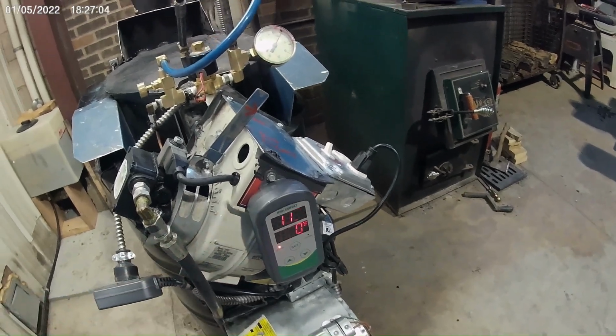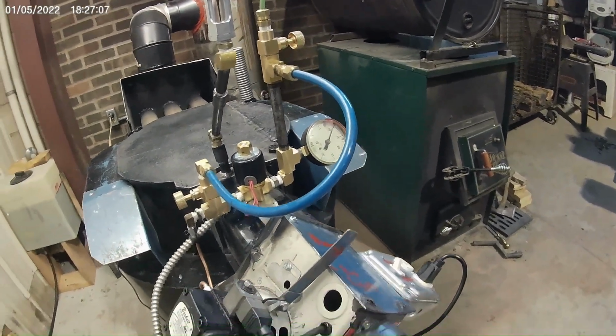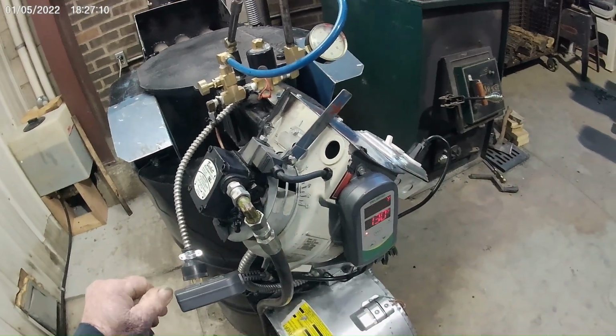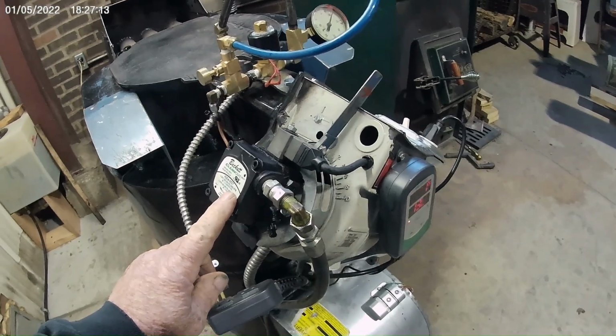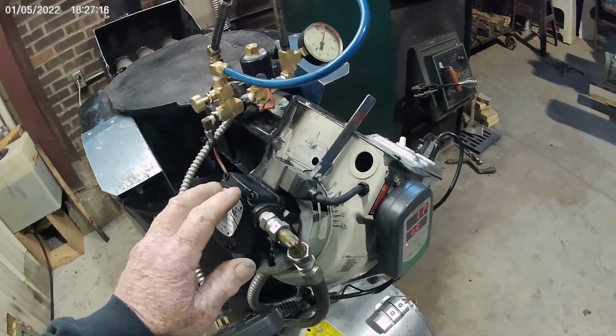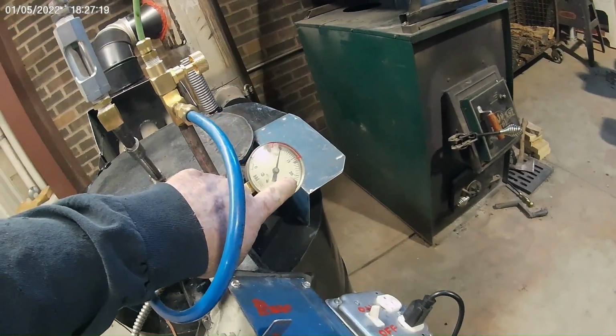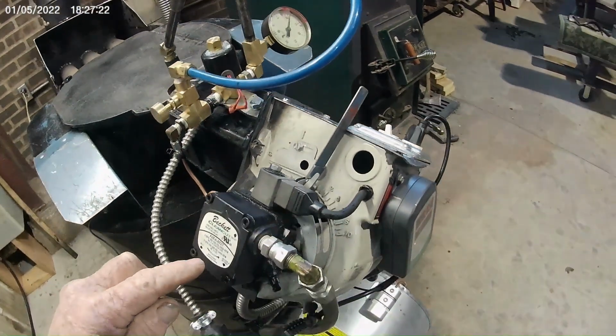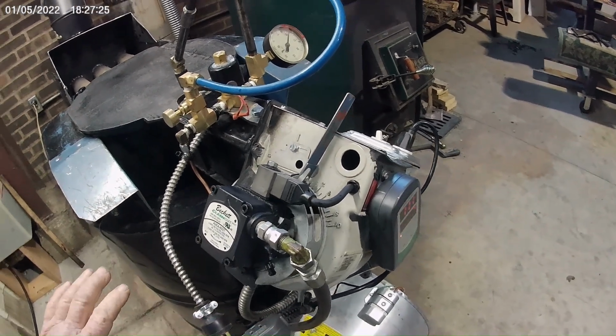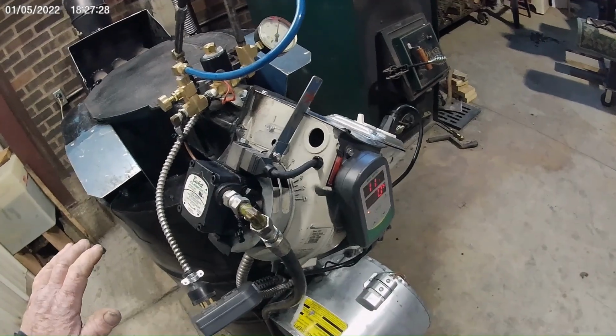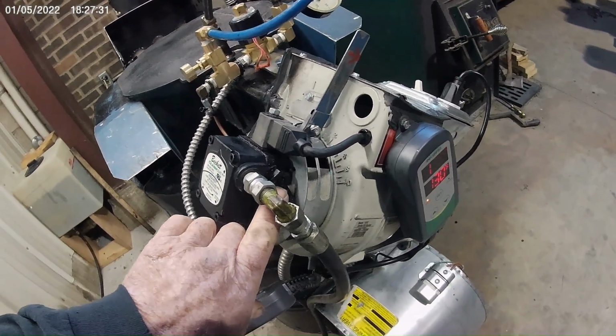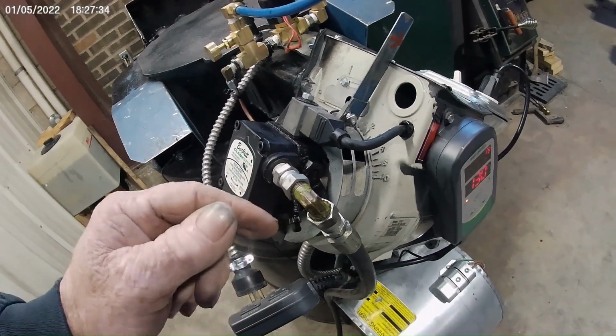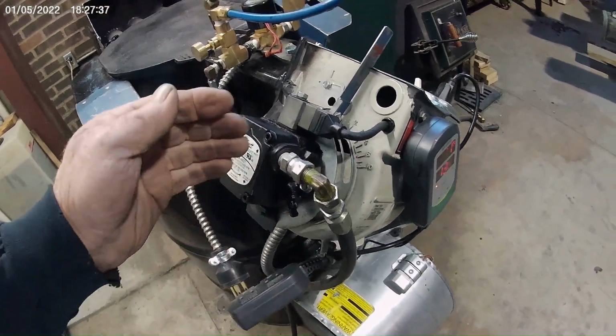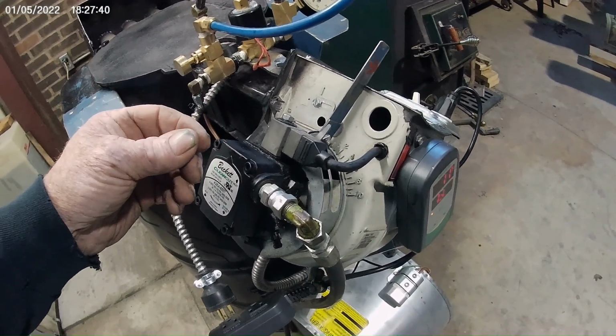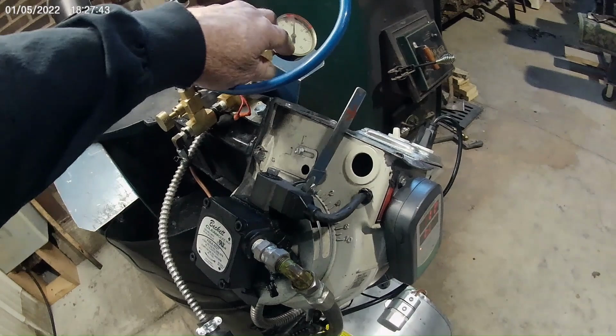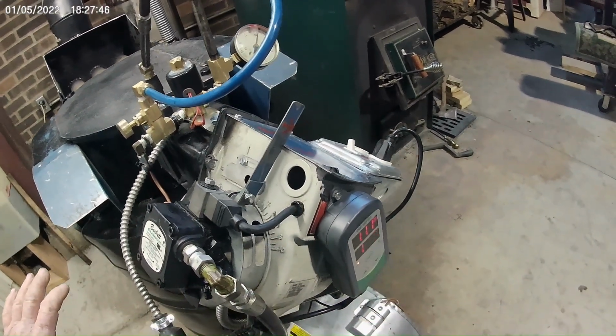114, holding steady. This particular stove was a single gear pump, and the maximum pressure that pump will put out right now is 20 pounds rather than what it's rated for, which was between 150 and 200 pounds. The way I did that was I took this relief valve out of here, pulled it out, drilled a hole in the end of it, and started cutting slots in it so it would relieve its oil pressure until I got it down to 20 pounds, which takes a little bit of patience.